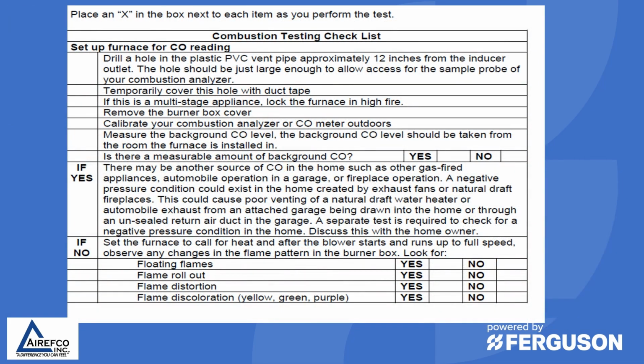Many manufacturers have a checklist, which is a very good idea when you're doing a combustion test on a gas furnace to determine whether the secondary heat exchanger is defective or not. These checklists take you through the process and make sure that you're not missing anything.